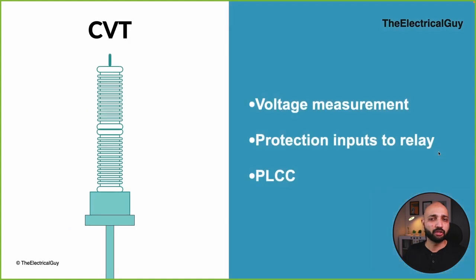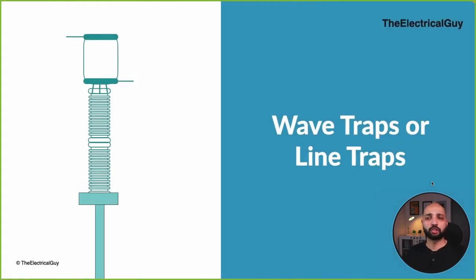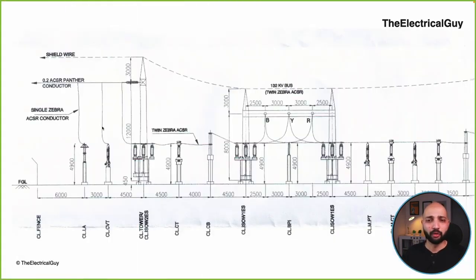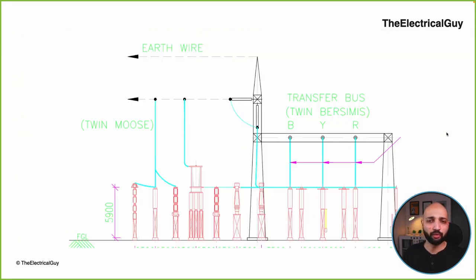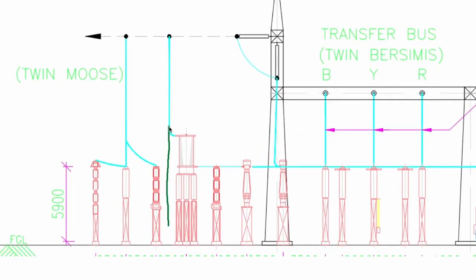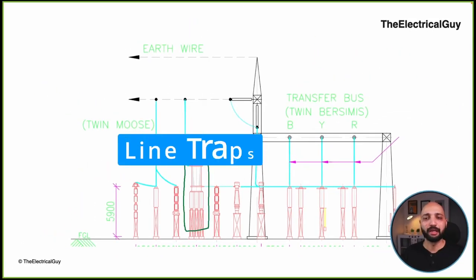So to summarize the functions of CVT, first of all, it is a voltage transformer which is used for voltage measurement, plus it also gives inputs to the relay for protection purpose, and it is also used for PLCC, that is power line carrier communication application. Now moving on, let's talk about the wave traps. In this particular substation, wave traps are not used, but not to worry, I have another layout where the wave traps are used. So you can see right here, this particular equipment is a wave trap, or it is also called a line trap.